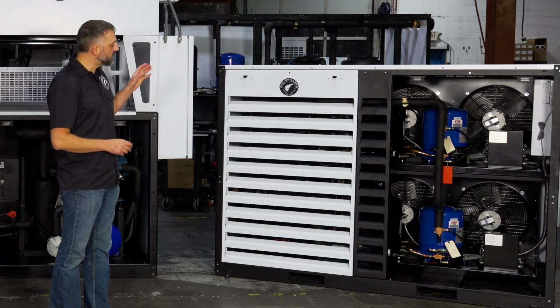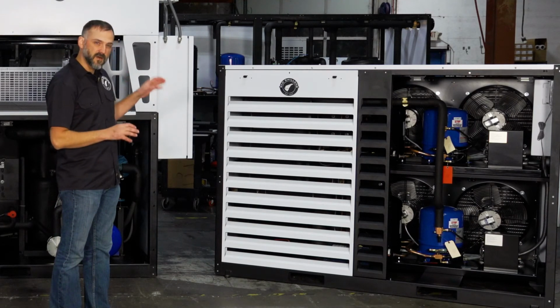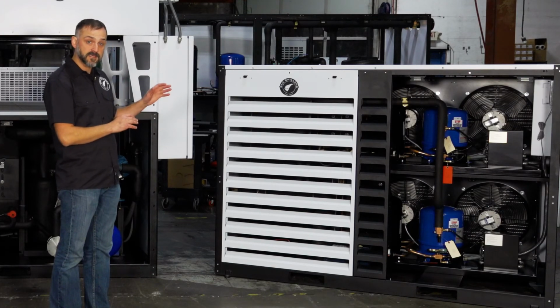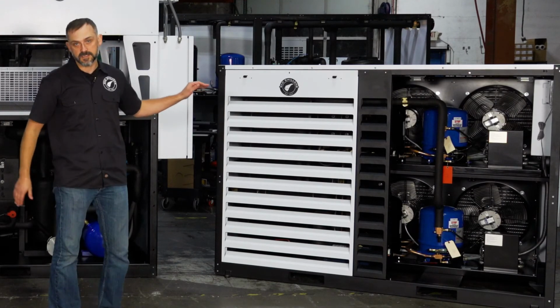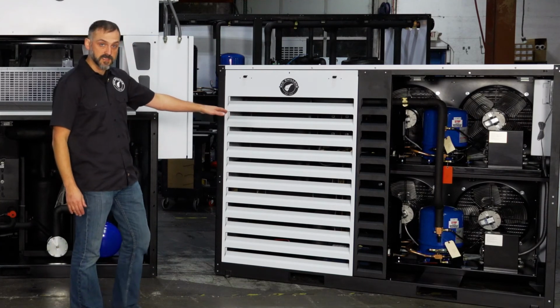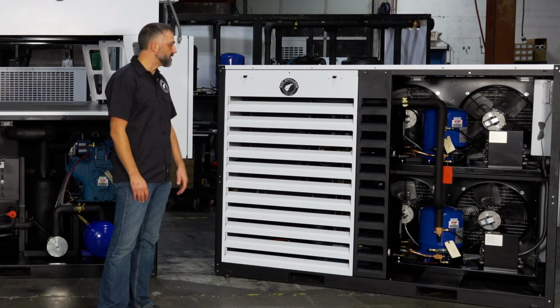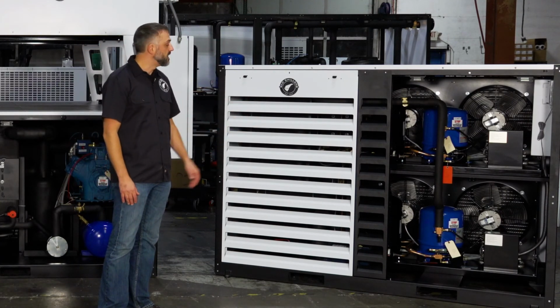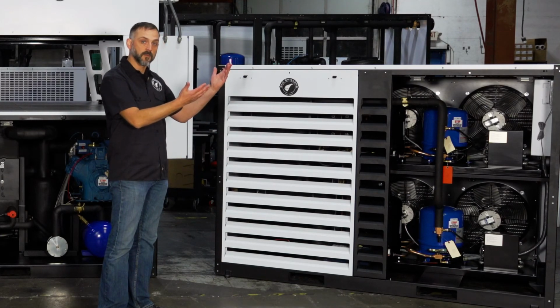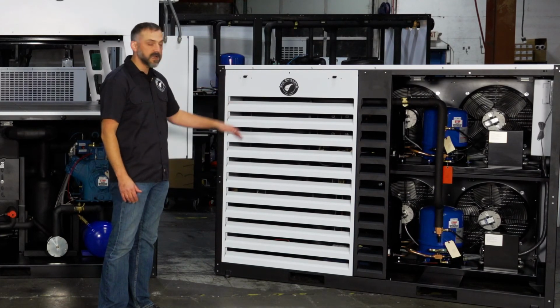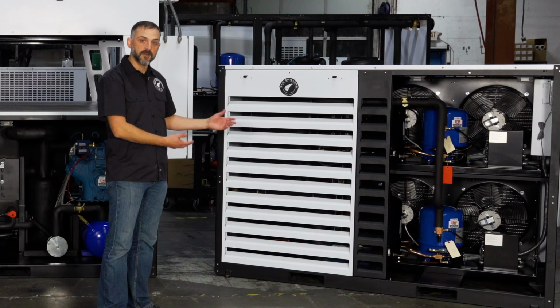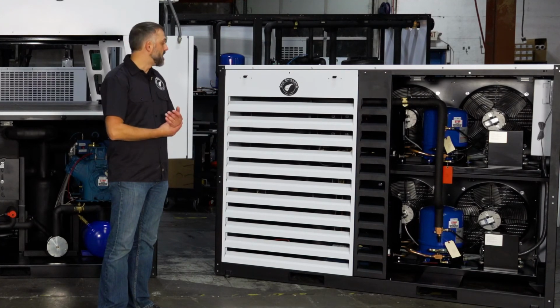It works good in a scenario where you might start a little smaller but not need its total capacity, because it has that redundancy just like this larger unit. You also will see 2 compressors here. If your demand's low, only one of them is going to run. If your demand is high, both of them are running together. They will cycle back and forth over the life of the chiller for equal runtime for each circuit.